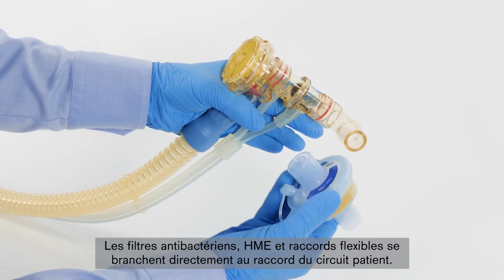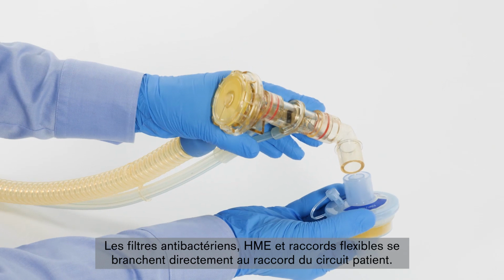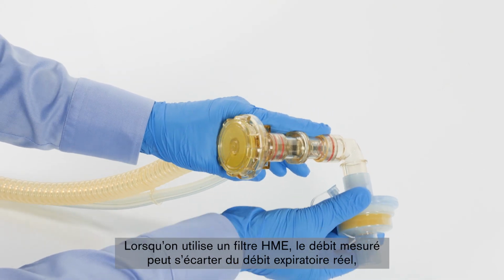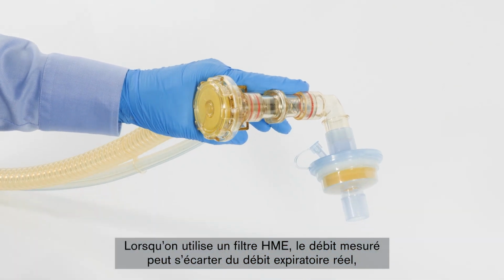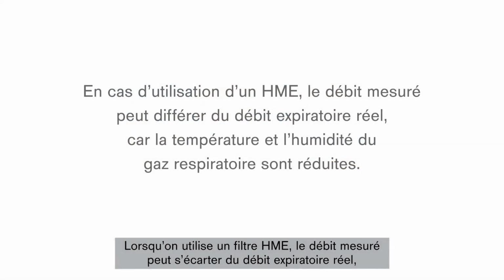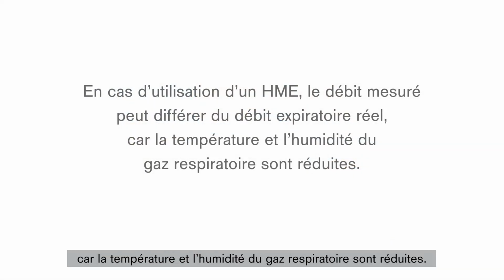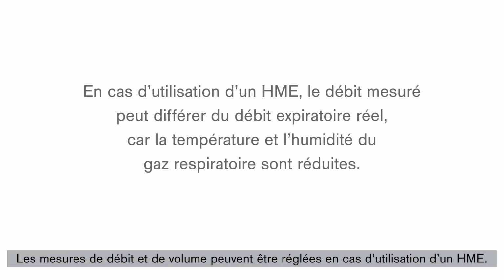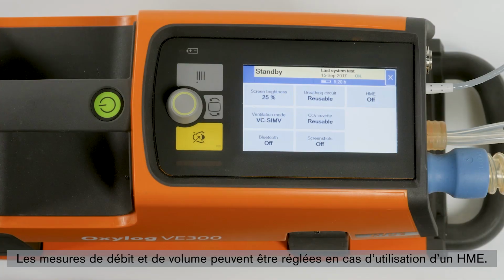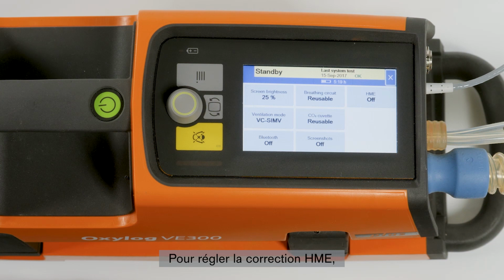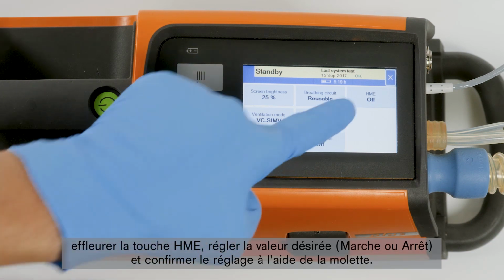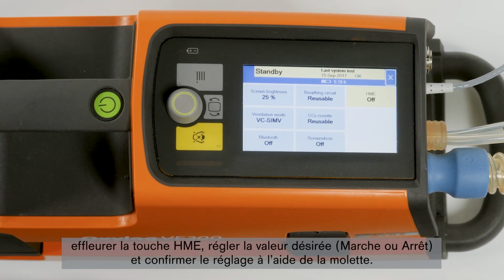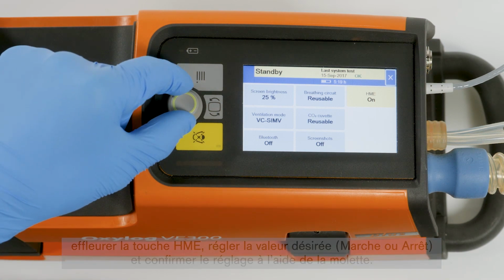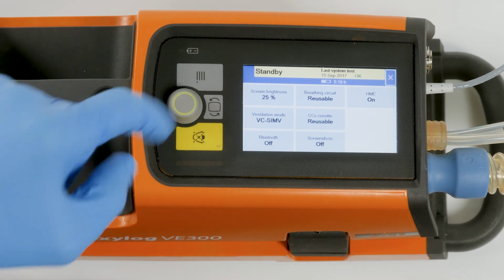A bacterial filter, HME or catheter mount is connected directly to the patient port of the breathing circuit. When using an HME, the measured flow may deviate from the actual expiratory flow because temperature and humidity of the breathing gas are reduced. The flow and volume measurements can be adjusted for use with an HME. To set the HME correction, touch the HME button, set the desired value, on or off, and confirm the setting with the rotary knob.